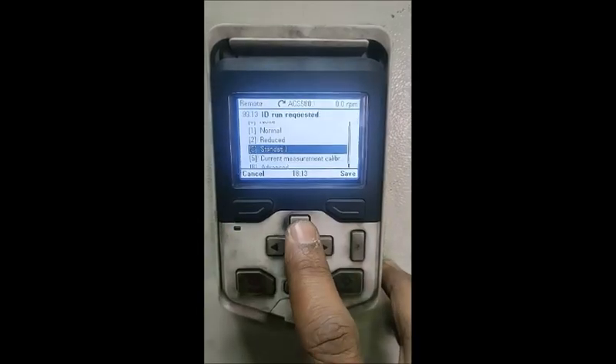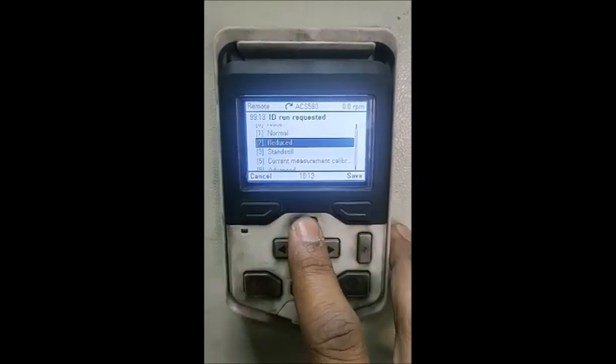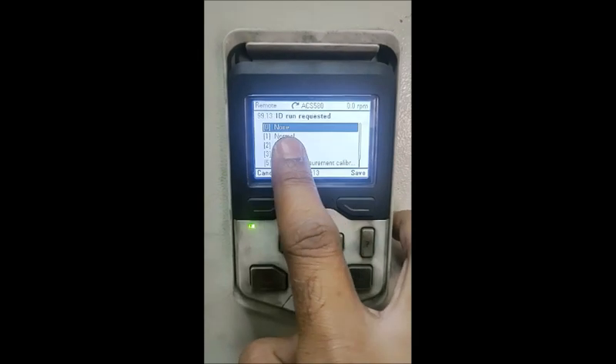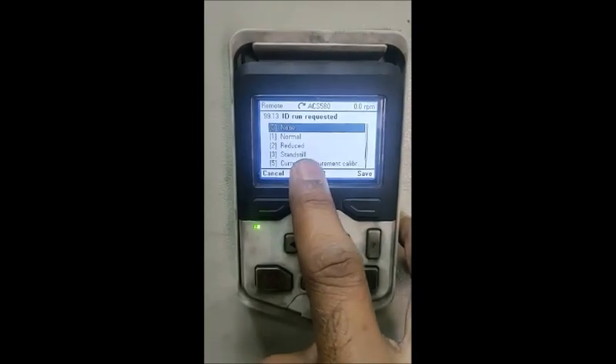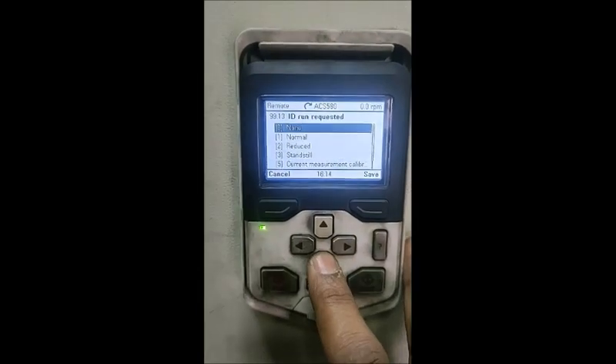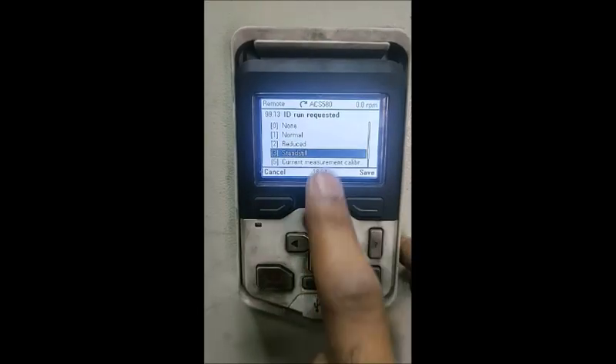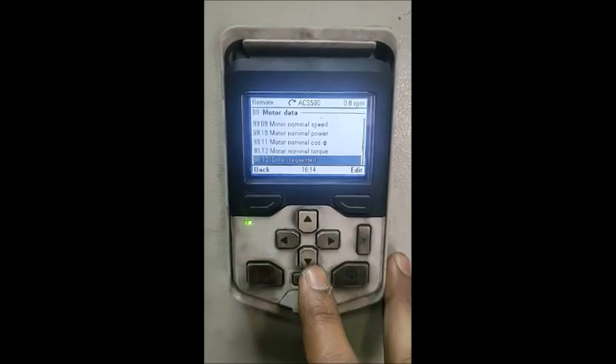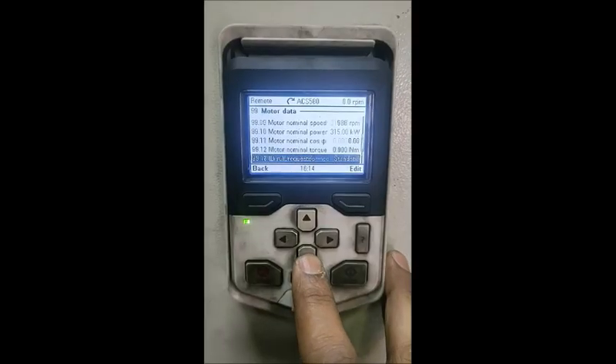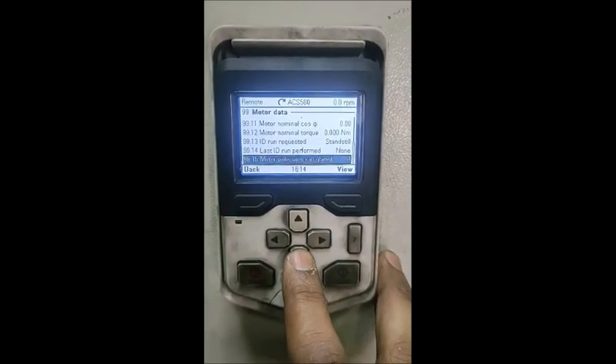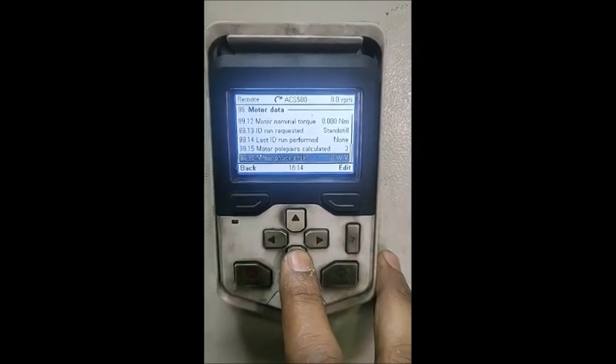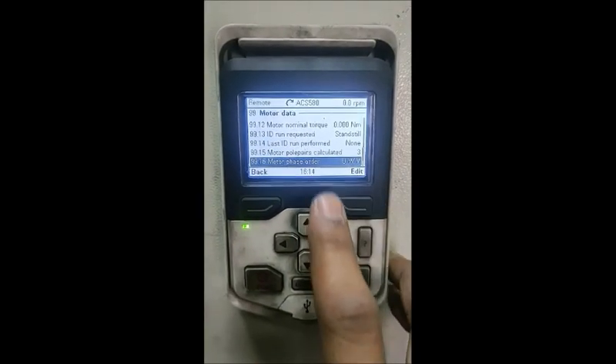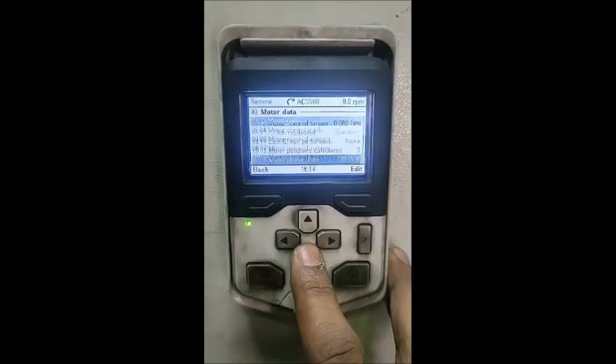This is important: ID run is performed. So 'ID run requested' — there are different options. Once the motor is in a coupled condition, we have to select standstill. Otherwise, you can select normal if it is free to rotate. Standstill is preferred. Once selected, we can also change the direction here.